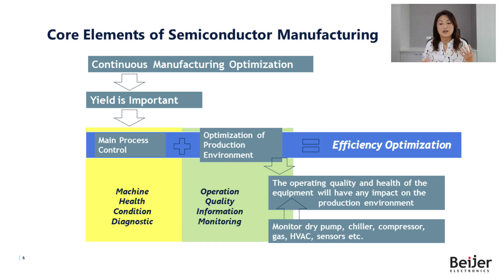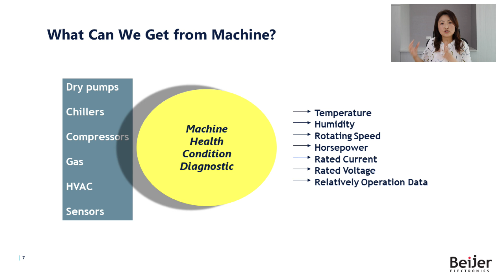For dry pump chillers, we also have to do machine health condition diagnostics. You can easily get data such as temperature, humidity, horsepower, and rated current. This data is already inside the machine, or you can get it while it's operating, but it's just never being paid attention to. It's either collected when you turn on the machine, from the operational settings inside the machine, or from the user manuals. All this data was actually there all the time, but in the past nobody paid attention to it. Now, when we monitor the main process and the environmental qualities, we also have to check the health condition of this surrounding equipment.